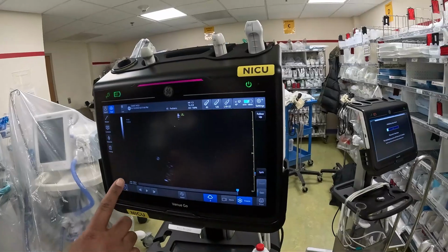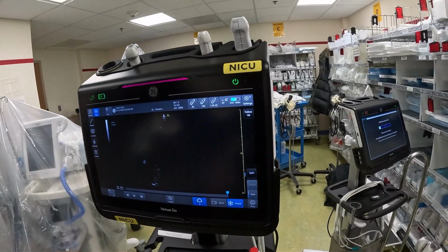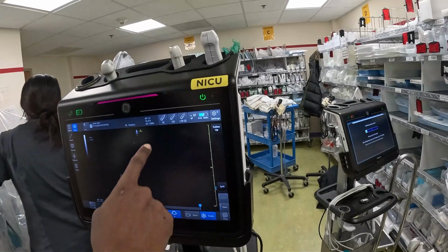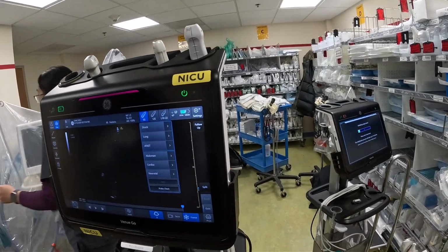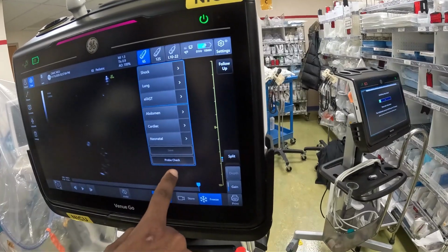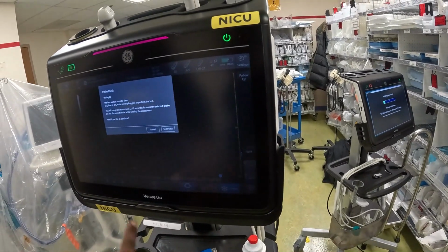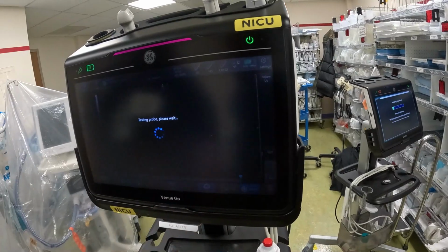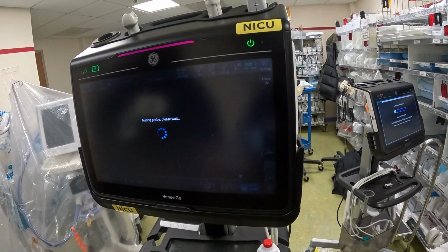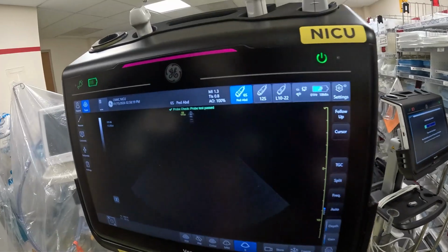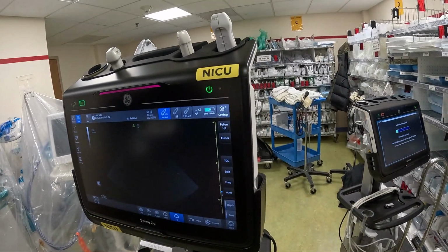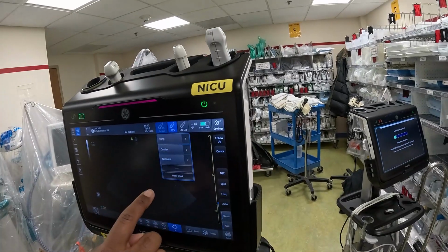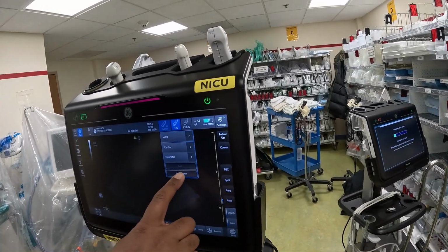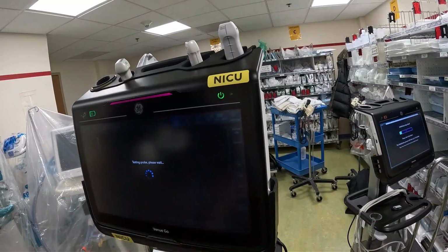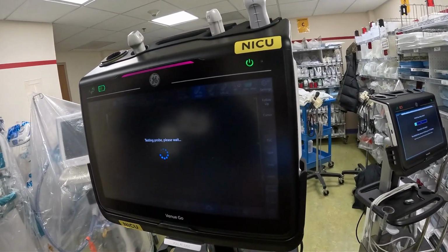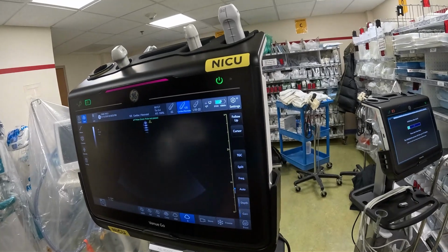On some ultrasounds at the very end, when you reattach the probes, it'll allow you to do a probe check. So you just click on the probe you want to check. You'll see a probe check button and click the probe check. This screen will pop up and you press test probe. Good to go. You see your probe test pass, and you can do it for the other two. Two for two.